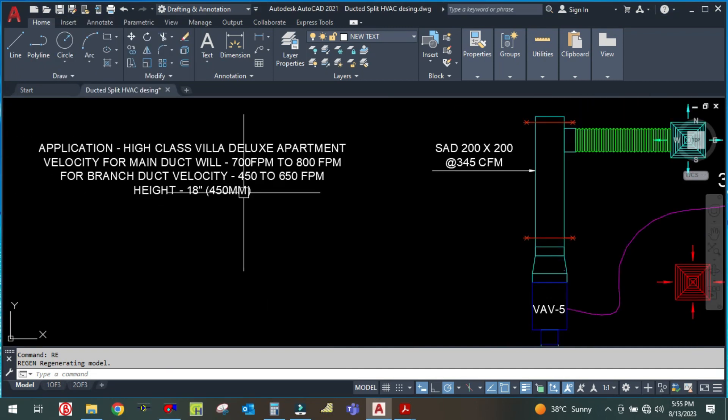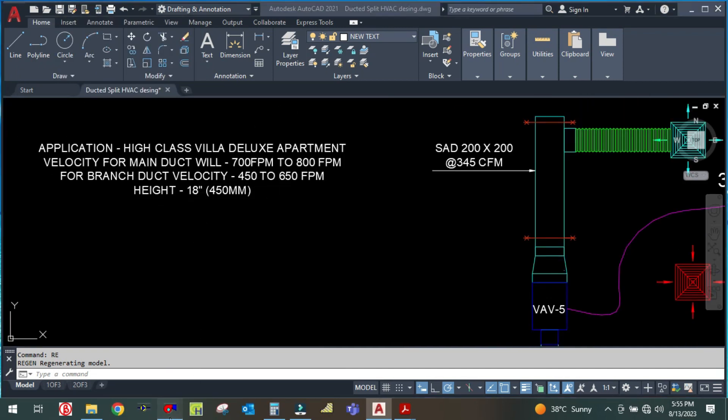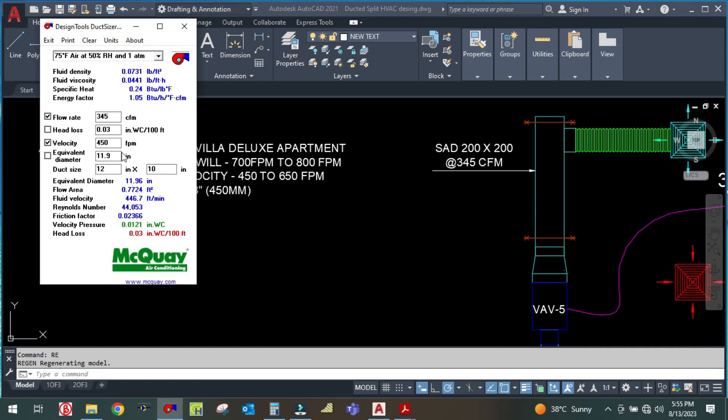For the branch duct you can see here 450 to 650 maximum, so let me increase it a little bit here to 550. And duct size, I am going to fix the height at 10 inches. So I am getting here 12 inch by 10 inch.